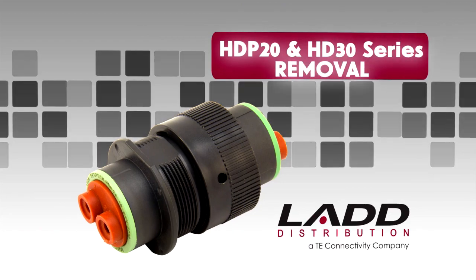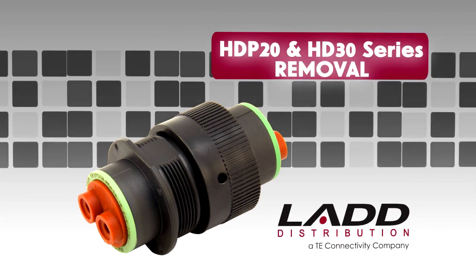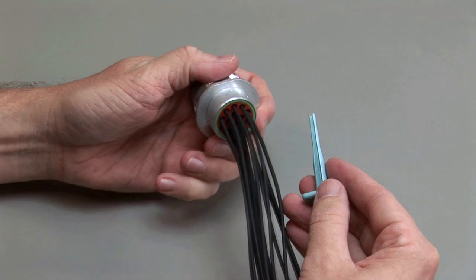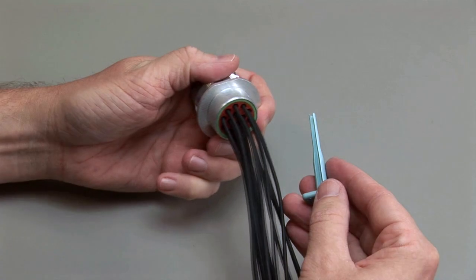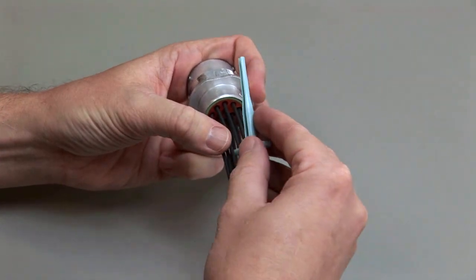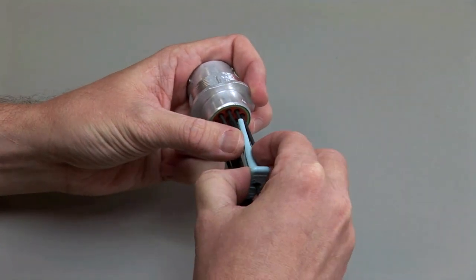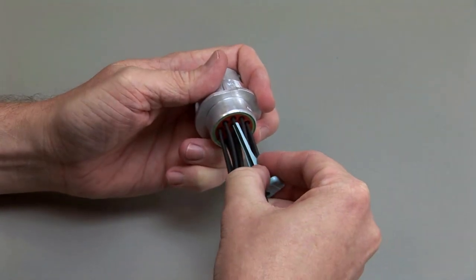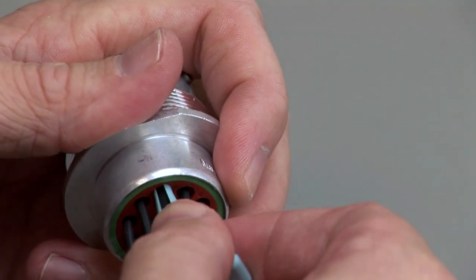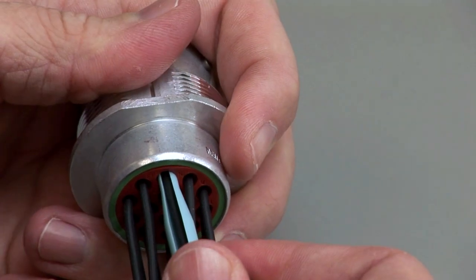HDP20 and HD30 contact removal. Hold the connector so the rear grommet is facing you. Using the correct size plastic removal tool, snap the tool over the wire so it will slide down the wire. Slide the tool along the wire into the cavity until it engages the contact and resistance is felt.